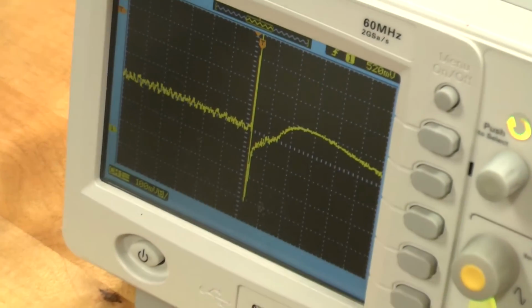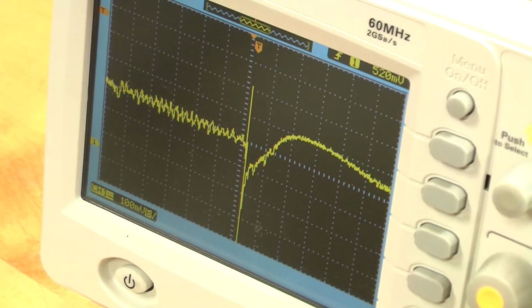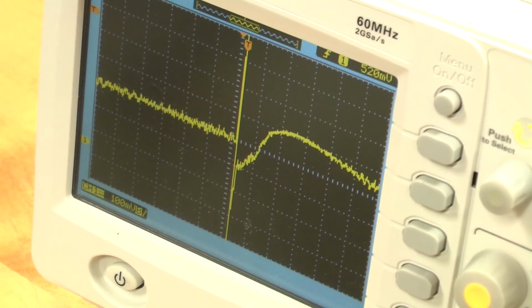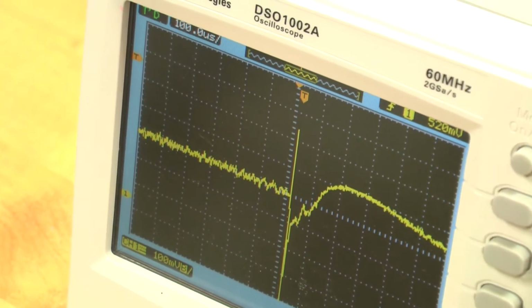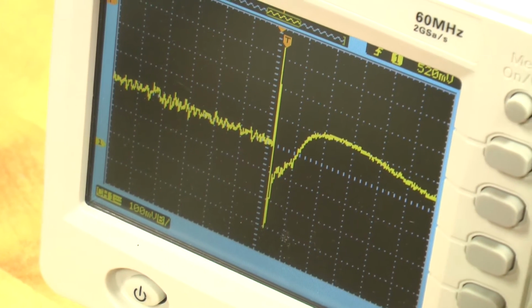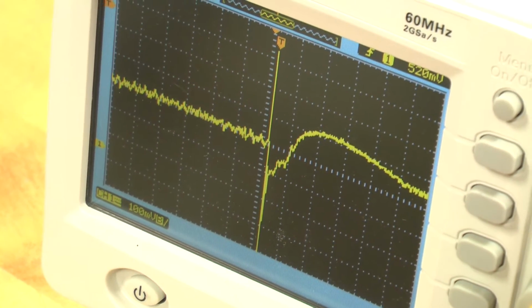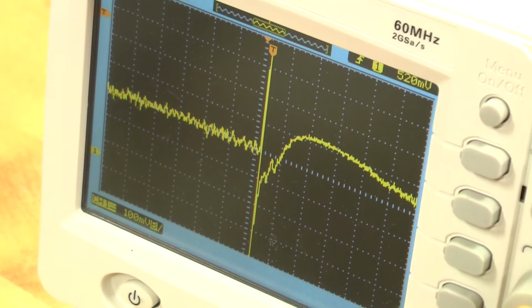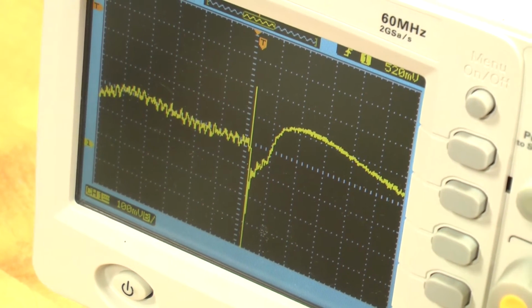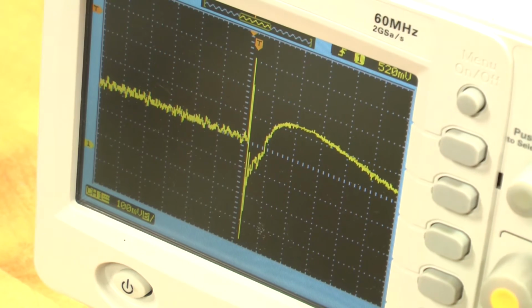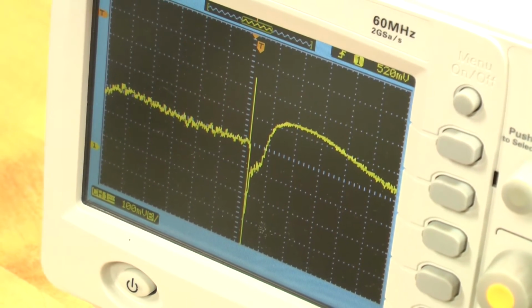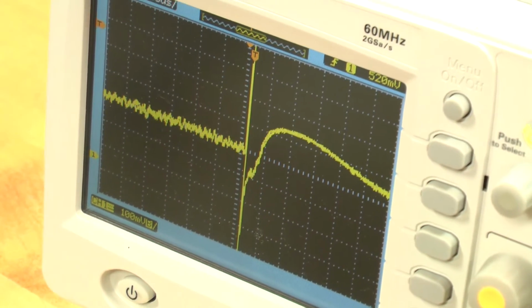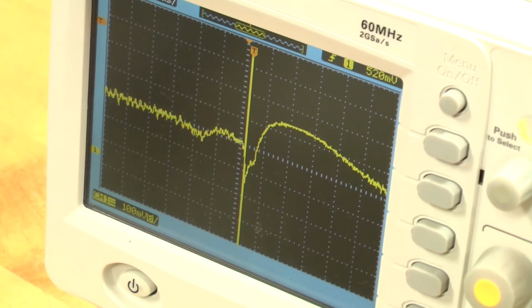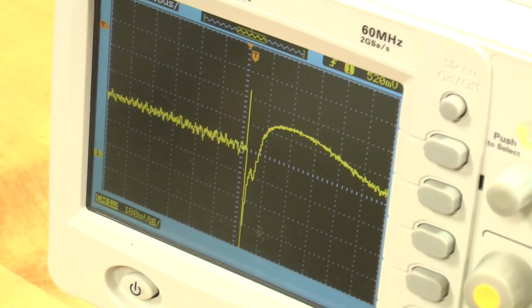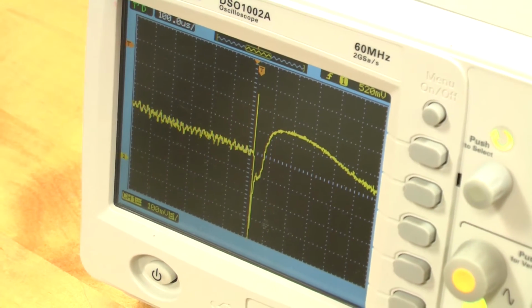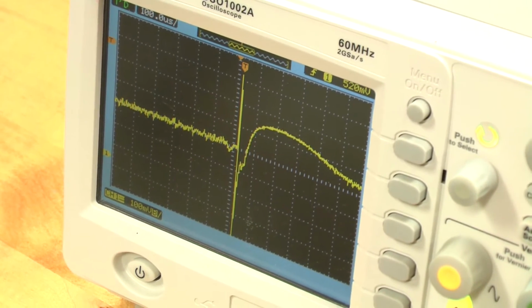That hump following the trigger, and you can see we're on 100 microseconds per division, means that there's about maybe a 20 microsecond delay before the power begins to discharge through the flash lamp, and the light begins to appear. We're still not lasing, we're still just producing incoherent light. But what you'll see is that when we do reach sufficient power that the unit begins to lase, we're going to get a distinct change in the hump that follows the trigger.